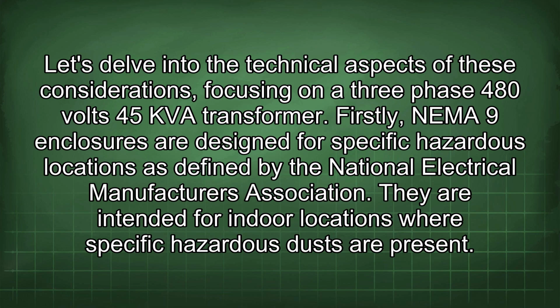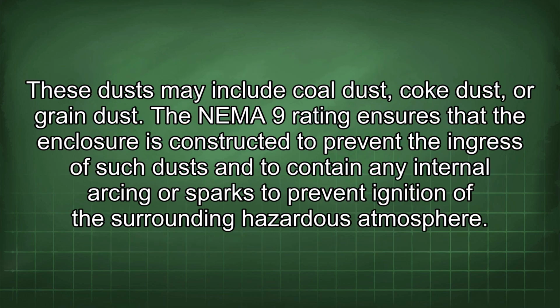Firstly, NEMA 9 enclosures are designed for specific hazardous locations as defined by the National Electrical Manufacturers Association. They are intended for indoor locations where specific hazardous dusts are present. These dusts may include coal dust, coke dust, or grain dust. The NEMA 9 rating ensures that the enclosure is constructed to prevent the ingress of such dust and to contain any internal arcing or sparks to prevent ignition of the surrounding hazardous atmosphere.